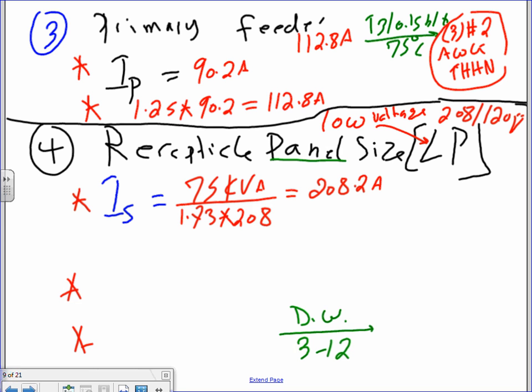So, I need to size my panel. Cool. So, you size it based on secondary. Then you're going to multiply it by 1.25 times 208.3. What was the size? I need 2 people to do the math here, please. It's 260.25. Yep. 260.25, good enough? 260.3.